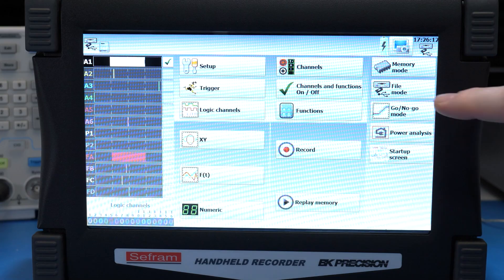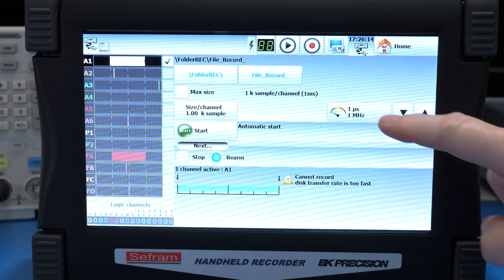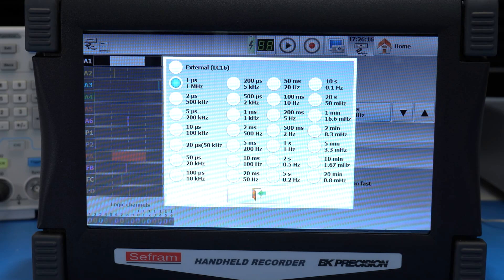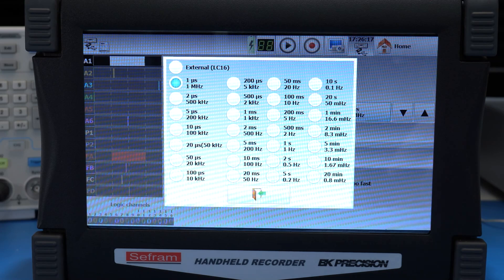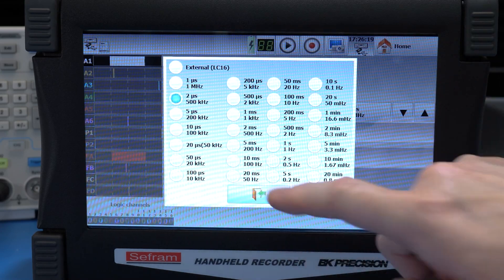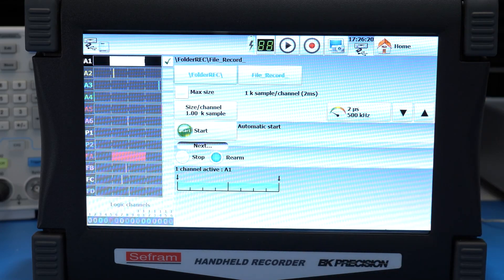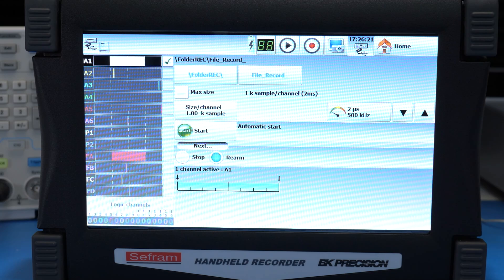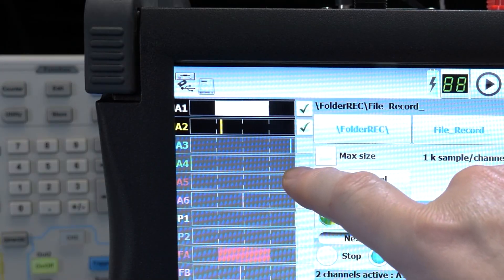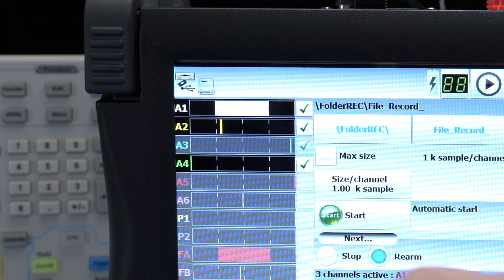I mentioned the sample rate, but only for real-time or what they call memory mode. In file mode, the recorder saves the samples to disk, and there the settings get a little confusing. Going into file, it looks like you can set a 1 microsecond rate. However, the max rate is actually 2 microseconds, and that is only for one channel. Enabling more channels means a slower sample rate.